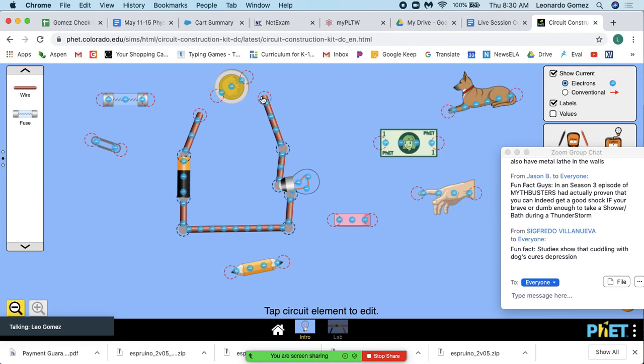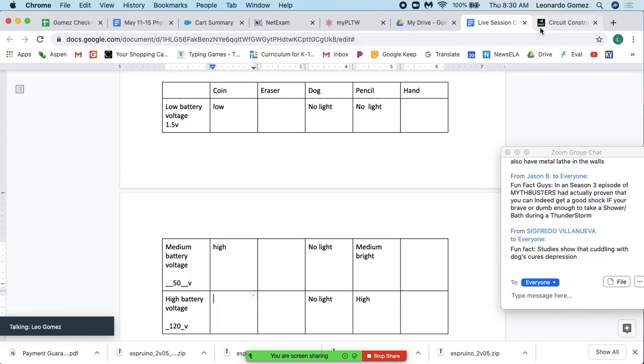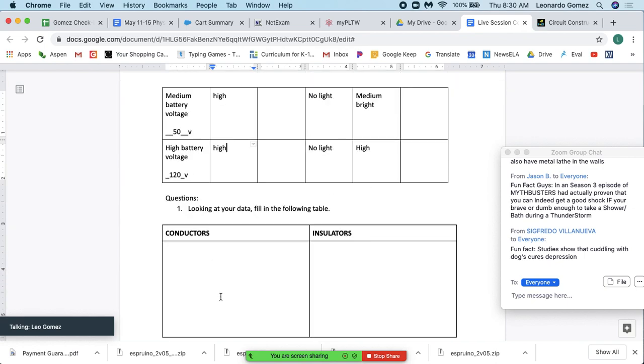And the problem is, sure, that would work for a little while, but if you ever run too much current through that coin, you could melt the coin into your fuse panel. It would get so hot from melting and all that, you could start fires. So that's kind of an issue with the fuses. And we've moved to breakers, which don't necessarily have issues around excessive heat building up and fire hazards. So the coin at 120 volts had an immense amount of light.